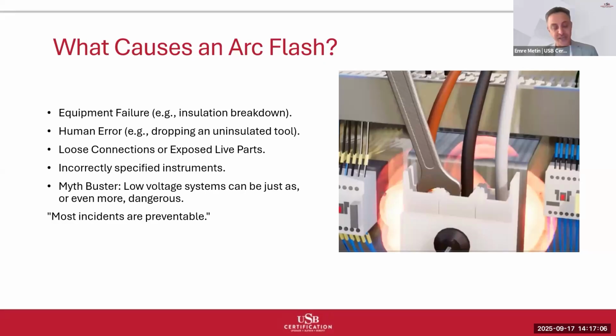Loose connections. Connections that loosen over time due to thermal cycling, vibration, or inadequate initial installation create high resistance paths that generate heat and eventually fail catastrophically. These failures can be particularly difficult to predict because the degradation happens gradually until the final failure is sudden and violent. Incorrectly specified instruments: using instruments or components rated for lower voltage or current than the application, or using components not designed for the specific application environment.